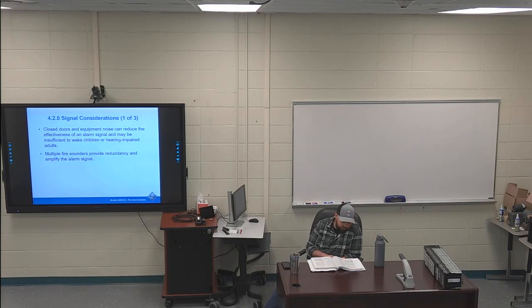Moving on to the next page, alarm sound level, second bullet point on page 32. I've got the second sentence in alarm sound levels highlighted. You have a couple of questions that come out of this one sentence. Public area audible alarms, so this is out in a public area, should be 75 decibels at 10 feet at a minimum, and a maximum of 120 decibels at the minimum hearing distance. You're going to have table 2 at the bottom.